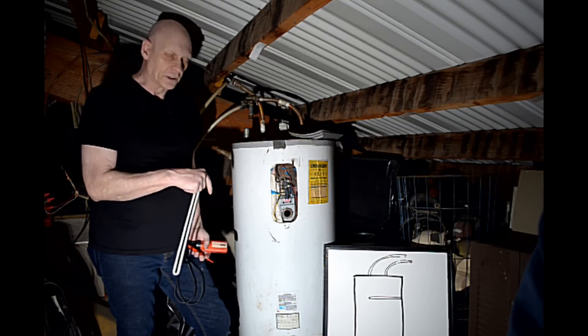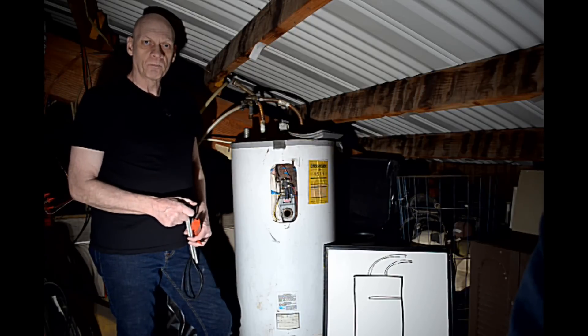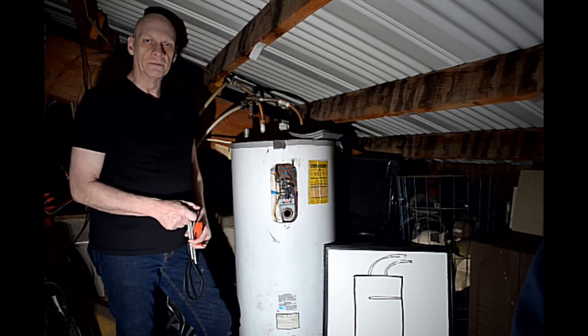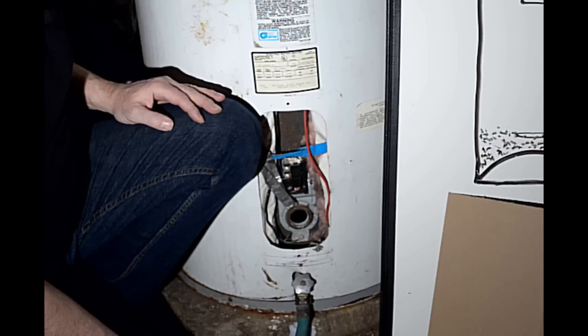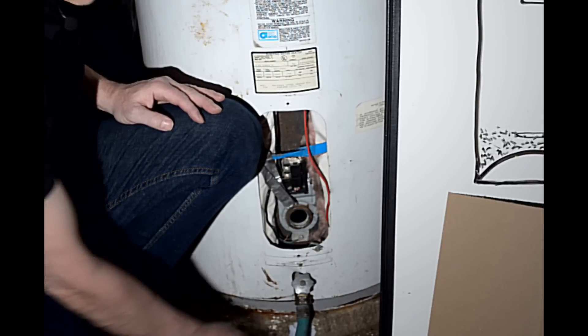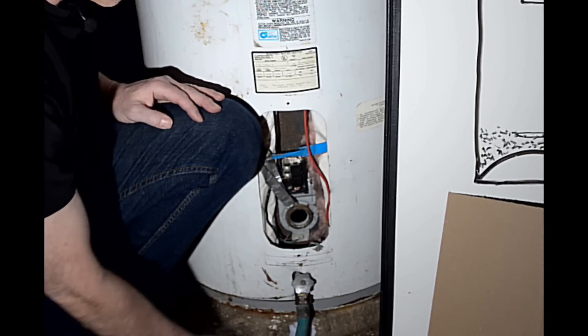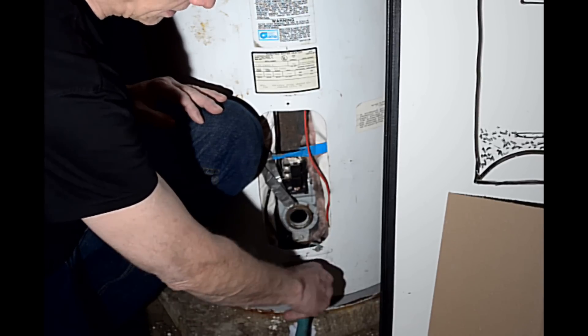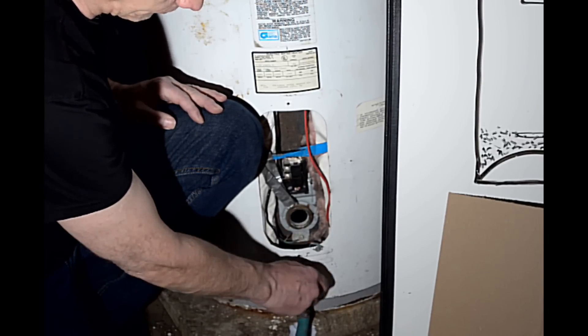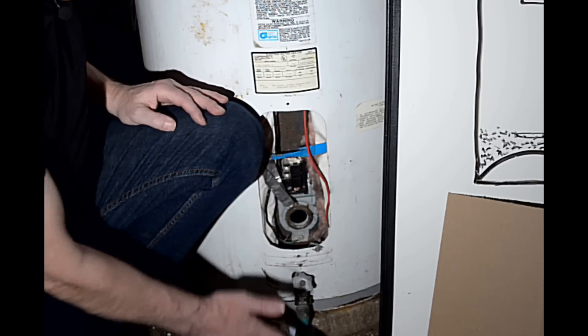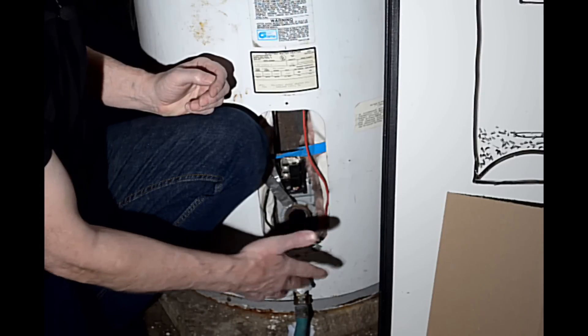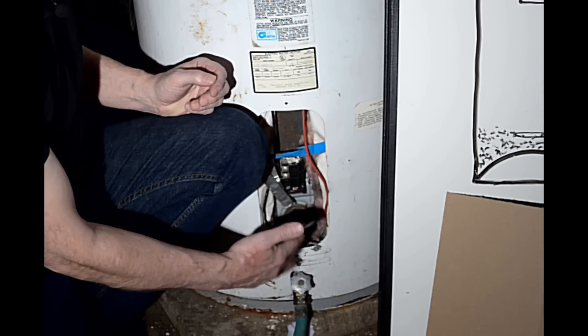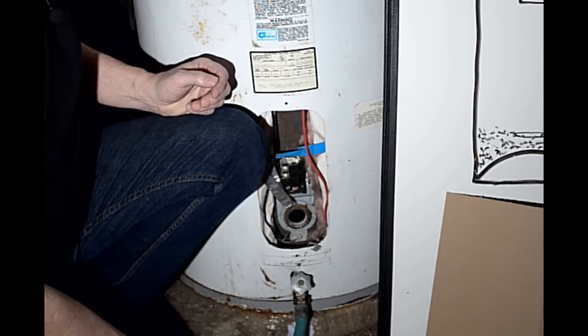Second thing we're going to do, hook a hose to the drain valve. When you get your hose hooked up to the drain valve, go ahead and turn your valve on. And it may not start to drain because there's no air coming in to allow the water to escape.